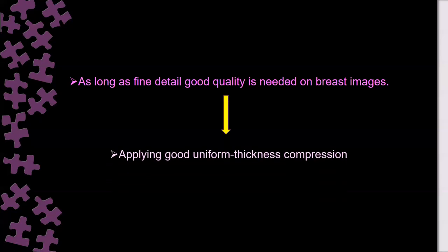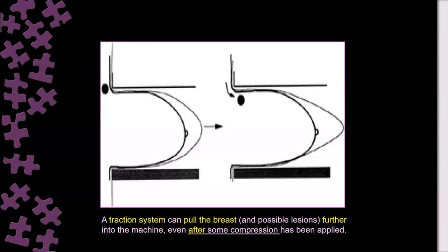So as long as fine detail quality is needed on the breast, we apply good uniform thickness compression. Okay, what happened here in these illustrations? This illustration demonstrates the posterior located lesions. When they applied the compression, it slipped back. It pulled out of the field of the view. But also, they discovered some modification in the machines to overcome these faults and these problems.